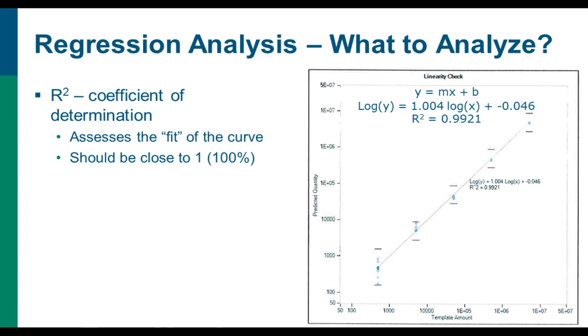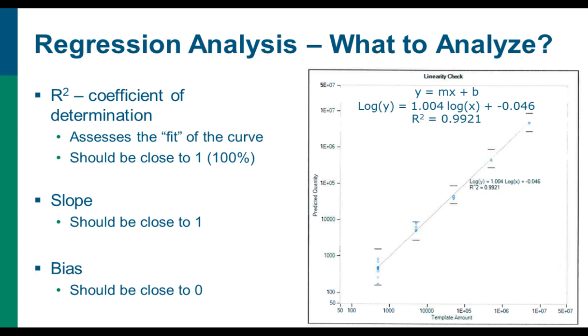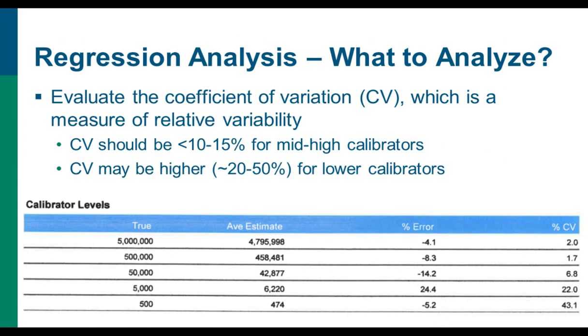Some people will think, oh, you just look at the r squared and you're done if you have a good r squared, but that's not true. Sometimes you can get a good r squared, but still not a very good curve. So in addition, you want to look at the slope, that m, and it should be close to 1. In this case, it's 1.004, so that's a very good slope. And then your b point, which is your bias, should be close to 0. There are no definitions of what is an acceptable r squared, slope, or bias. You just want to make sure that they're as close to 1, 1, and 0 respectively as possible. And if you have a high r squared, but your slope is not close to 1, or your bias is really high, 0.8 or 1, then you'll want to run a new curve. This is something you'll develop a feel for after a while, but there are no defined criteria for what makes it acceptable.